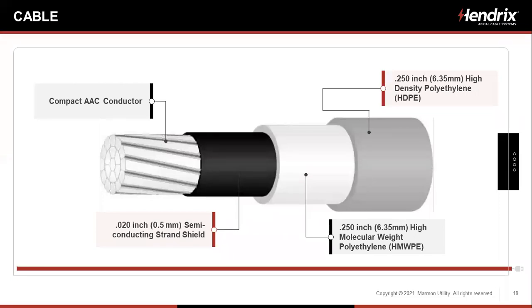We'll take a look briefly at the components. For the cable, we're using the same exact cable that we're using for 15, 25, 35, 46 kV. It's a 3-layer cable. It's compact, double AC. We know we're getting more ampacity. We don't need rated tensile strength because those phase conductors are not under any mechanical tension. So the double AC will give us lower weight, higher ampacity, and the ability to compact it so that we'll use less polyethylene. Polyethylene is expensive, so we want to reduce that cost. And with the lower diameter, we're going to have a lower profile to wind and ice and what have you.